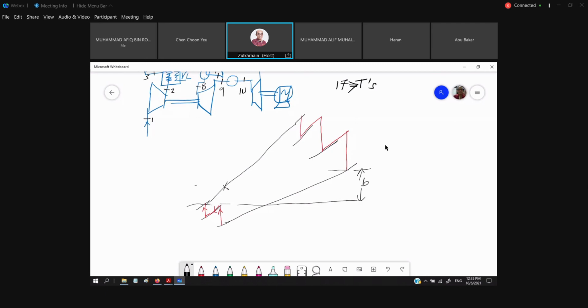And this increment of temperature, we refer to as A. This is the maximum available temperature difference. So to get the heated-up air temperature right here, we need to look at the ratio of A over B, which is usually given, and this is given the name of what? Guys, what is the name of this A over B? What is the ratio? Thermal ratio.